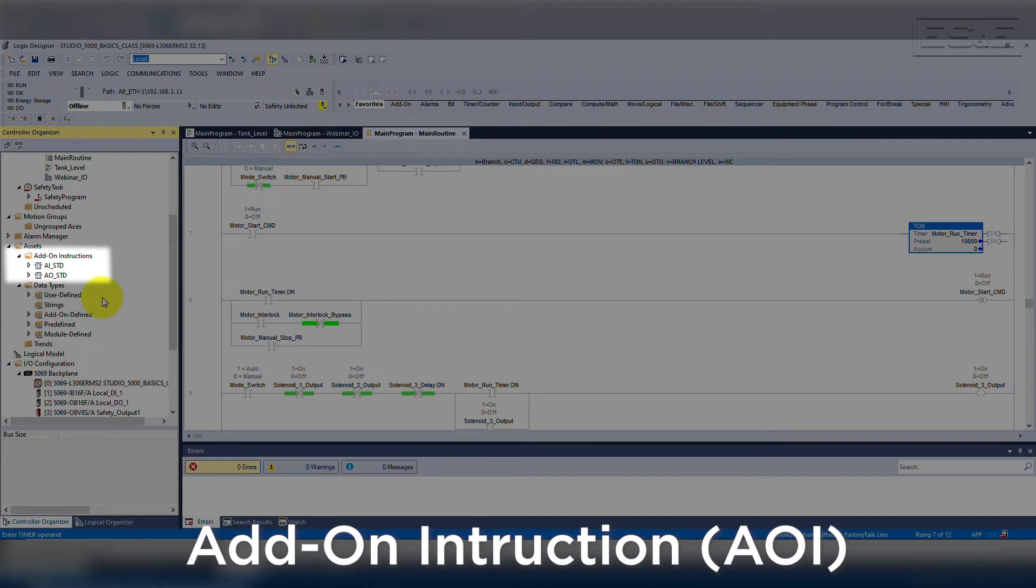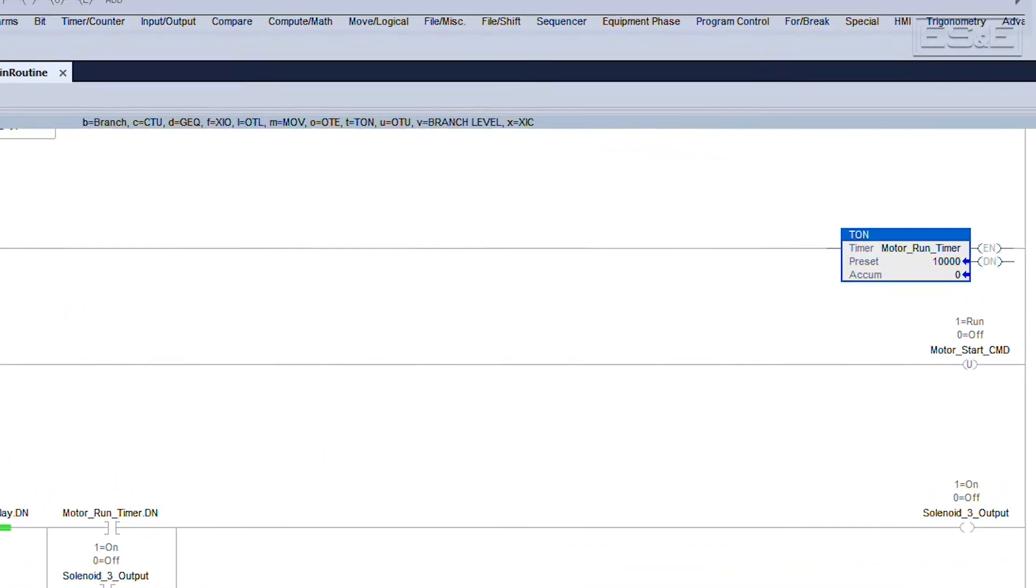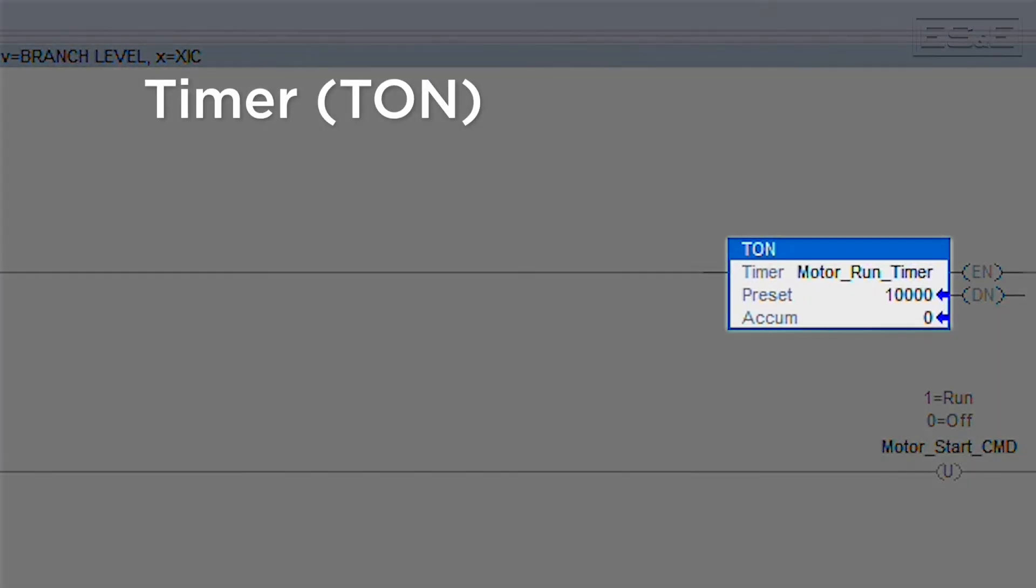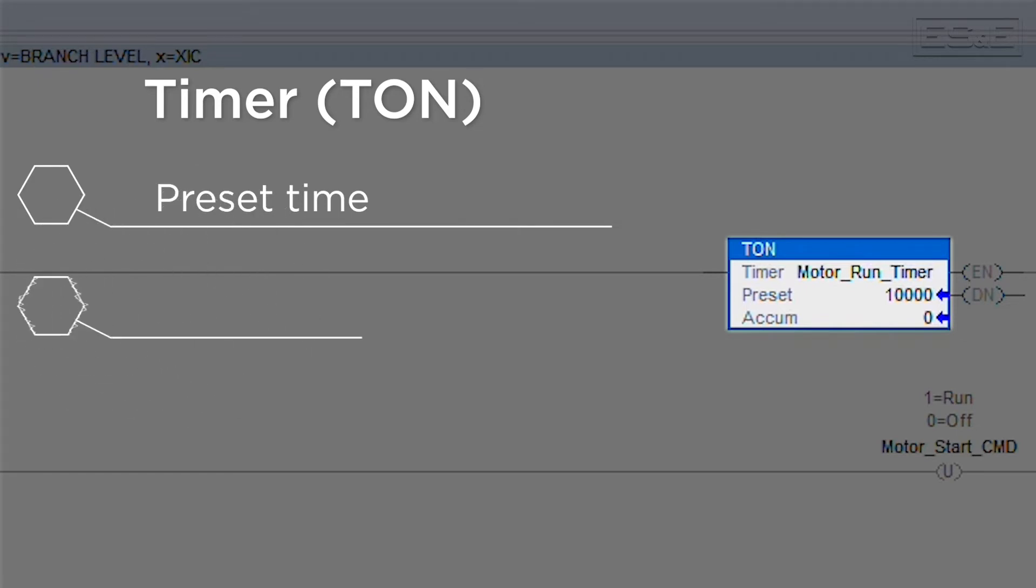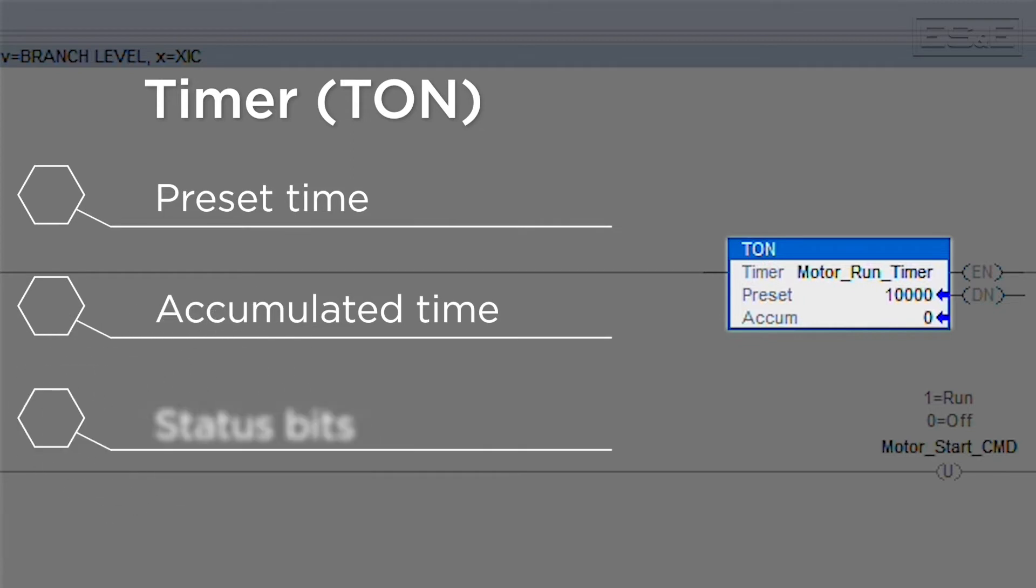An AOI is a snippet of code and corresponding tags that can be used repeatedly. A very simple and common AOI is a timer or TON instruction. The instruction is made up of a preset time for the counter to reach, an accumulated time based on how long it has been active, and a few status bits such as done or timing. Each time that you add a TON instruction, you will always get the same tags, and the logic will always execute the same based on those tags and the configuration of the timer.